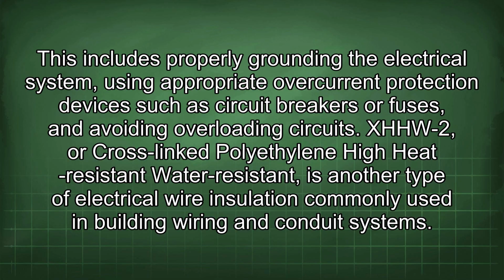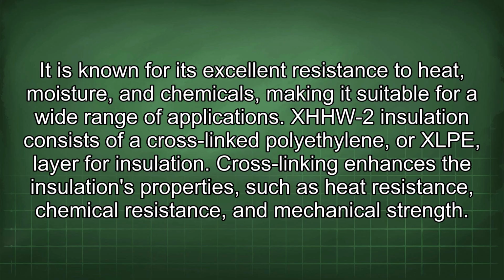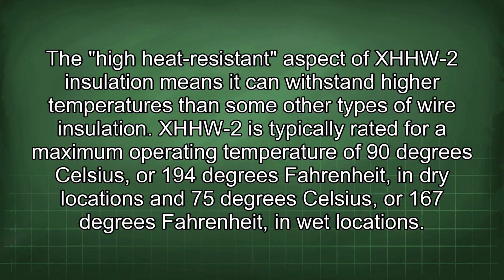XHHW-2, or cross-linked polyethylene high heat resistant, water resistant, is another type of electrical wire insulation commonly used in building wiring and conduit systems. It is known for its excellent resistance to heat, moisture, and chemicals, making it suitable for a wide range of applications. XHHW-2 insulation consists of a cross-linked polyethylene, or XLPE, layer for insulation. Cross-linking enhances the insulation's properties such as heat resistance, chemical resistance, and mechanical strength. The high heat resistant aspect of XHHW-2 insulation means it can withstand higher temperatures than some other types of wire insulation.